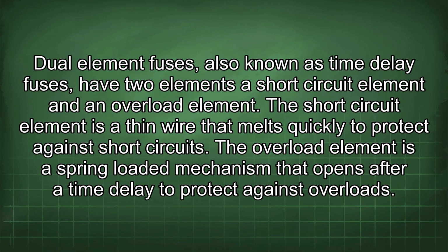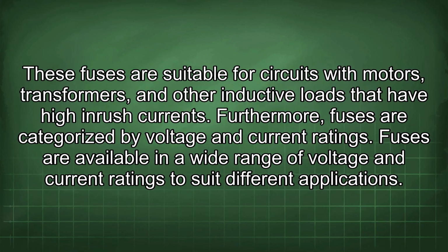Dual-element fuses, also known as time delay fuses, have two elements: a short-circuit element and an overload element. The short-circuit element is a thin wire that melts quickly to protect against short circuits. The overload element is a spring-loaded mechanism that opens after a time delay to protect against overloads. These fuses are suitable for circuits with motors, transformers, and other inductive loads that have high inrush currents.